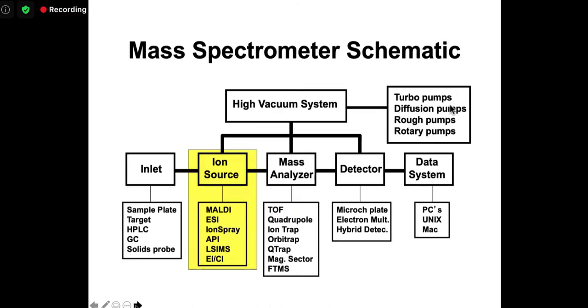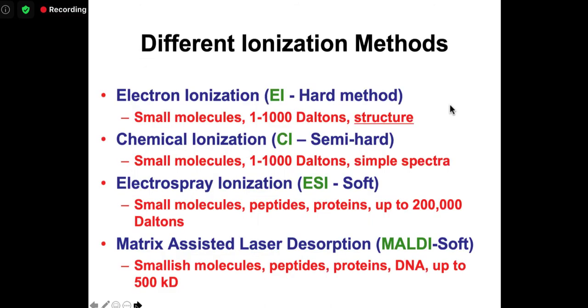Mass spectrometers have an ionizer called an ion source — it can be electrospray, ion spray, atmospheric pressure ionization, electron impact, or chemical impact. They all run high vacuum systems to ensure nothing contaminates the ions. In terms of different ionization methods: EI and CI are used for GC-MS, typically with lower mass limits around 700 Daltons maximum. Some are called hard ionization methods like electron impact, and some are soft ionization methods like electrospray (ESI) or MALDI. ESI is the most common method for ionizing in LC-MS and is used not only for metabolomics but also proteomics. MALDI is used in metabolomic imaging.